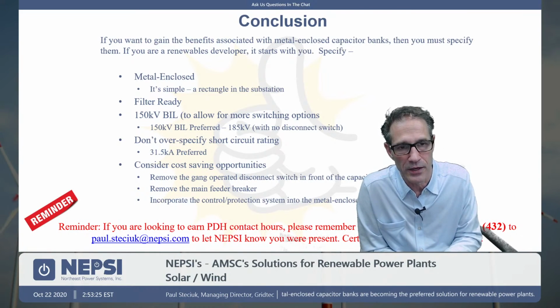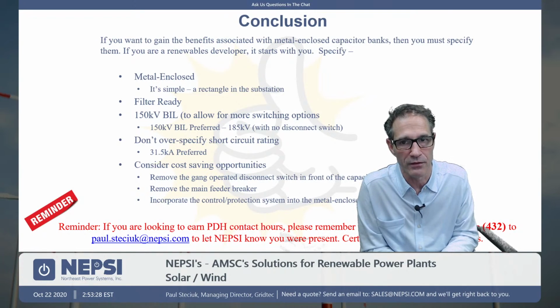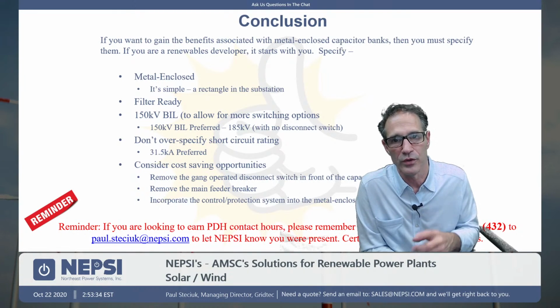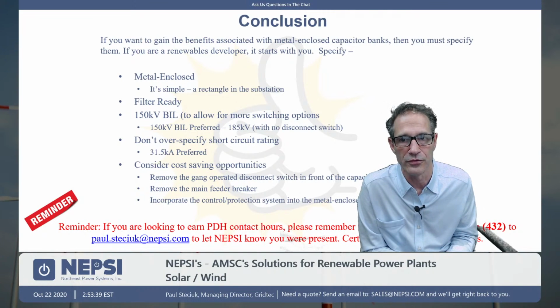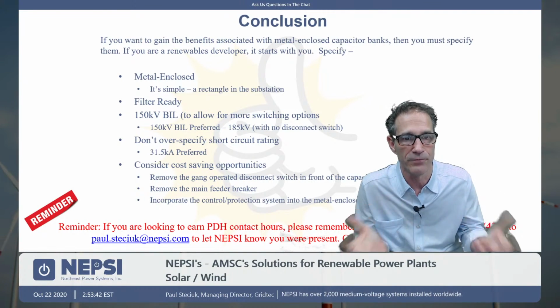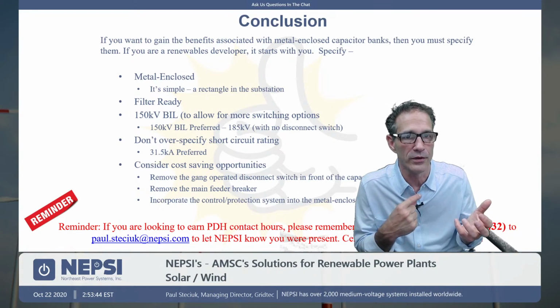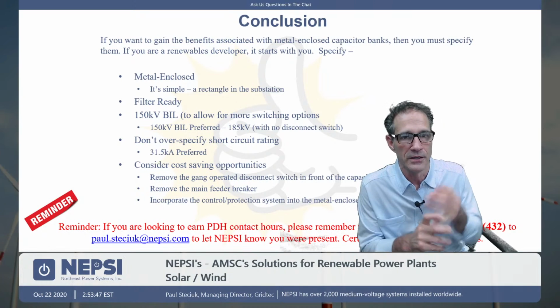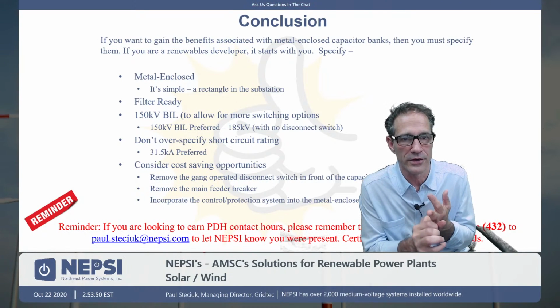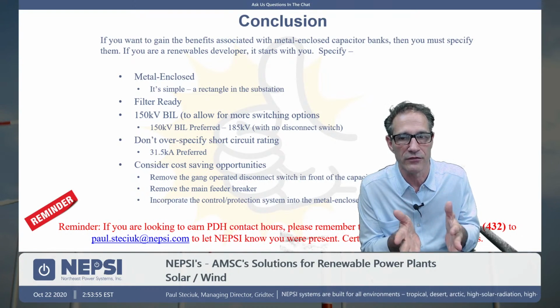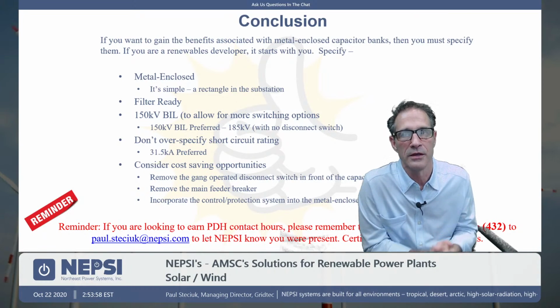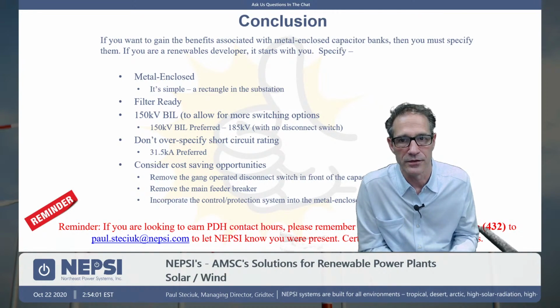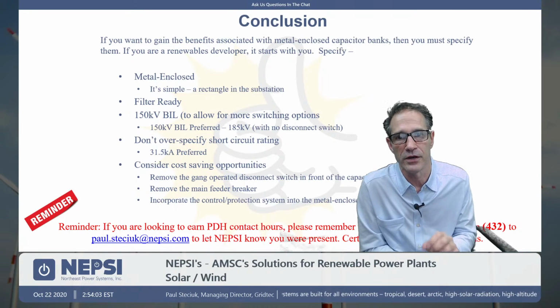Specify 150 kV BIL, not 200. And if you do that, it allows us to use more components within our gear. It gives us more choice, and we can pass cost savings on to you. It is well within the IEEE standards to use 150 kV BIL. We're not exposed to the environment. We don't have concerns that the open air guys have, which is contamination of the insulators or bird strike against the insulators themselves and flashover. Because we're inside the enclosure, we're protected from the environment. We don't have to worry about rodents in the 150 kV BIL. It makes sense at that point. So 150 kV BIL is preferred.